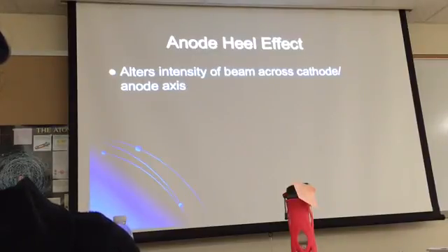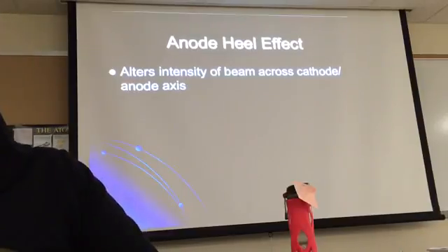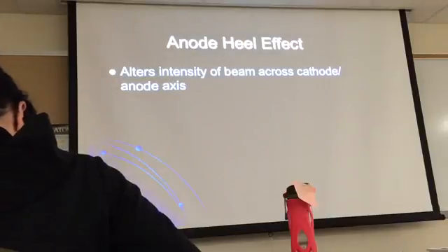But what is the heel effect? What you're saying is what most people will say, but that is really the effect. But why do we have that? Why is the intensity higher on the cathode side? For thicker parts, so you want higher intensity on the thicker part.